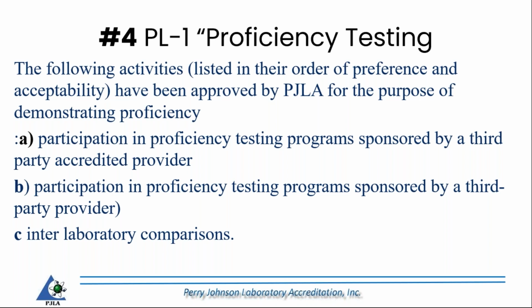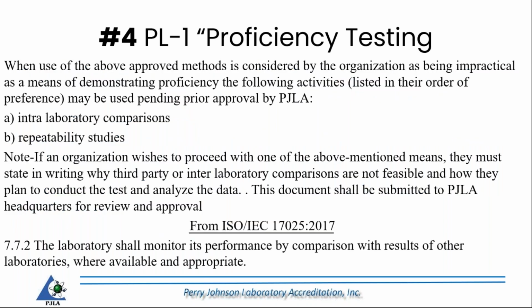approved by PJLA. An interlab comparison, yourself and another competent organization testing the same sample or similar or artifact and comparing your results in a meaningful way. That's all perfectly fine as far as a scheme. I think sometimes where we had issues here is there's also specifies intra-lab and repeatability studies. So this can still be done.